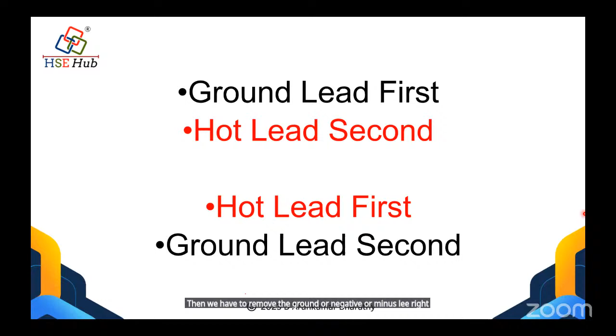Whenever we take a measurement, we should always position the ground lead first, then use the hot lead, that is the plus lead, second, to take the measurement. Similarly, when removing the probes, first we remove the hot lead or plus or phase, then we remove the ground or negative or minus lead. This is the practice we have to follow.